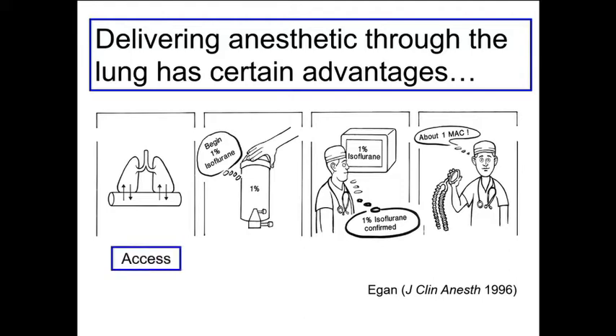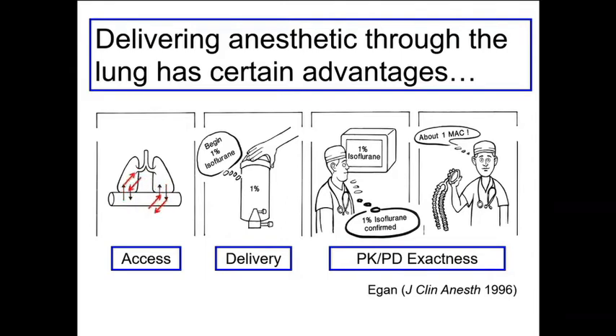When you gain access to the circulation through the lung, you've got a very unique situation. You have an equilibration process that takes place. And that means that by using an agent-specific vaporizer for delivery, you're able to set an upper limit above which the partial pressure, the concentration, cannot rise. And that is a very distinct advantage.